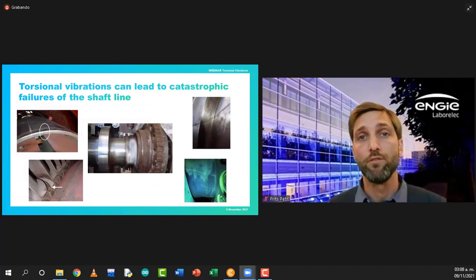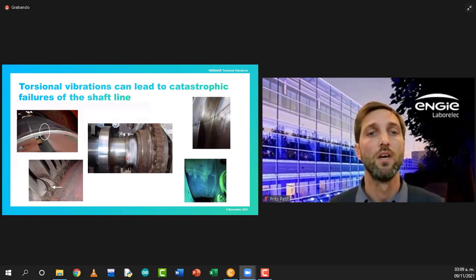Some examples that we've experienced in the past, but also more recently, are seen here. We will have more details on them later on, but typically what you can see is large cracks in main shafts of the rotor. So for instance, here in a compressor rotor shaft, you can see the typical 45-degree angle, which is also a feature of torsional vibrations. The initiation typically occurs at a stress concentration, typically in a fillet transition from a lower diameter to a larger one. Besides main shafts, we also have cracks appearing in retaining rings, for instance, or in the generator slots. Some incidents of blade failure have been reported as well, and we will have an example later on as well.